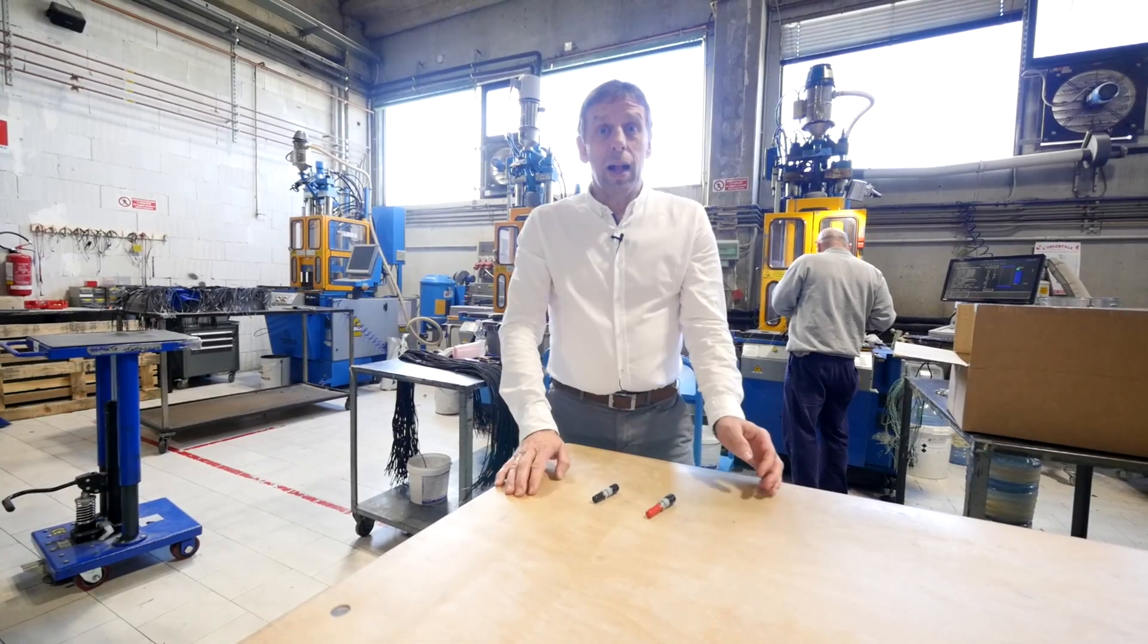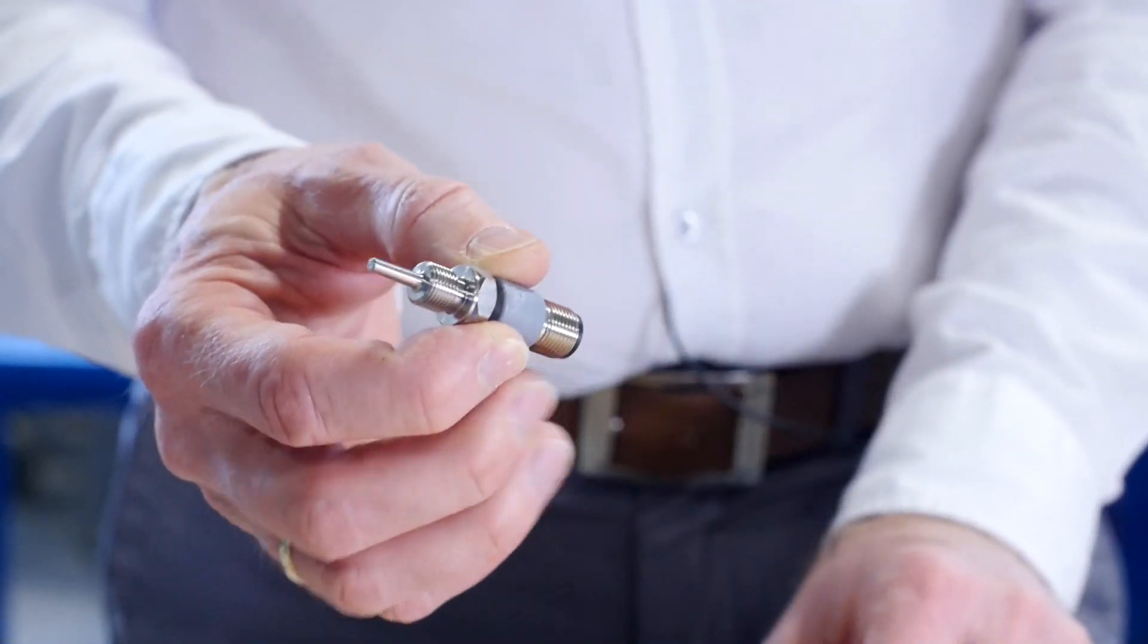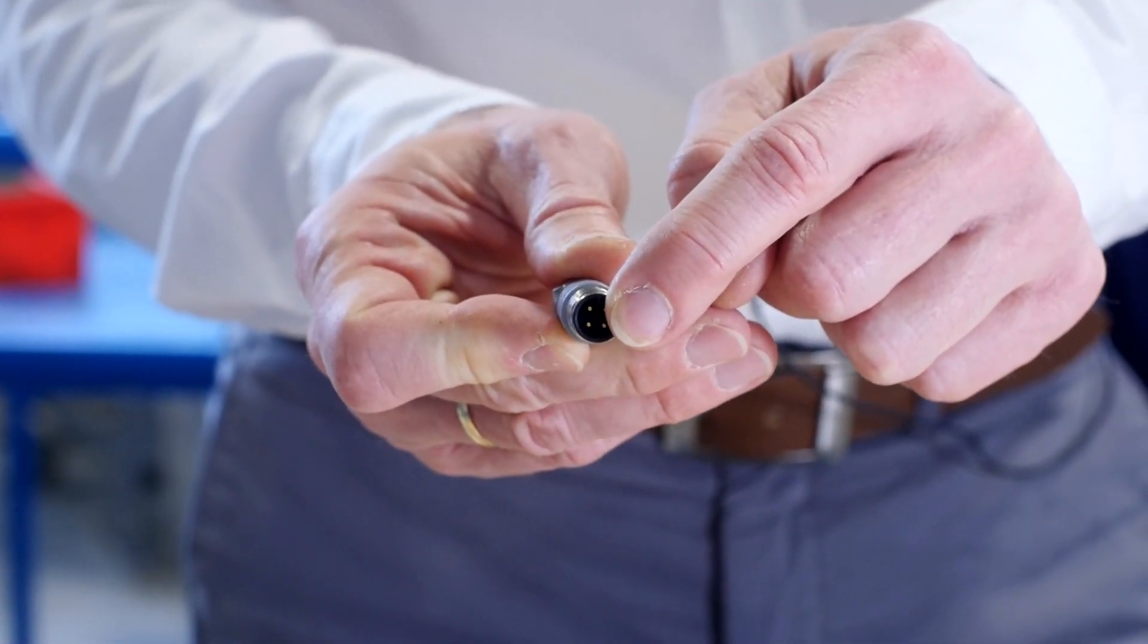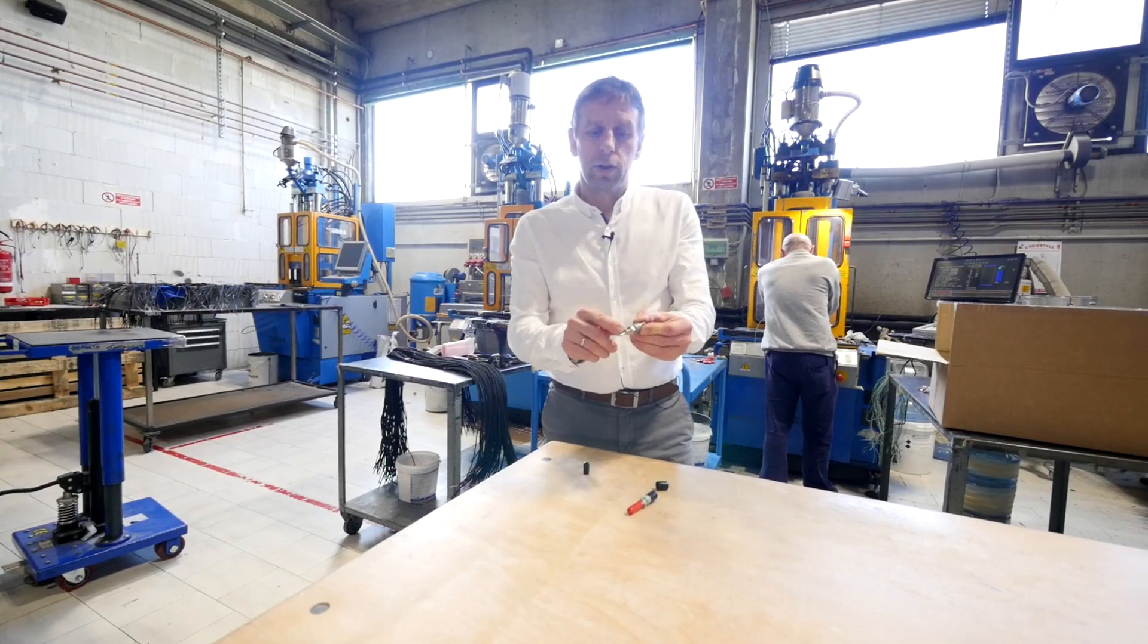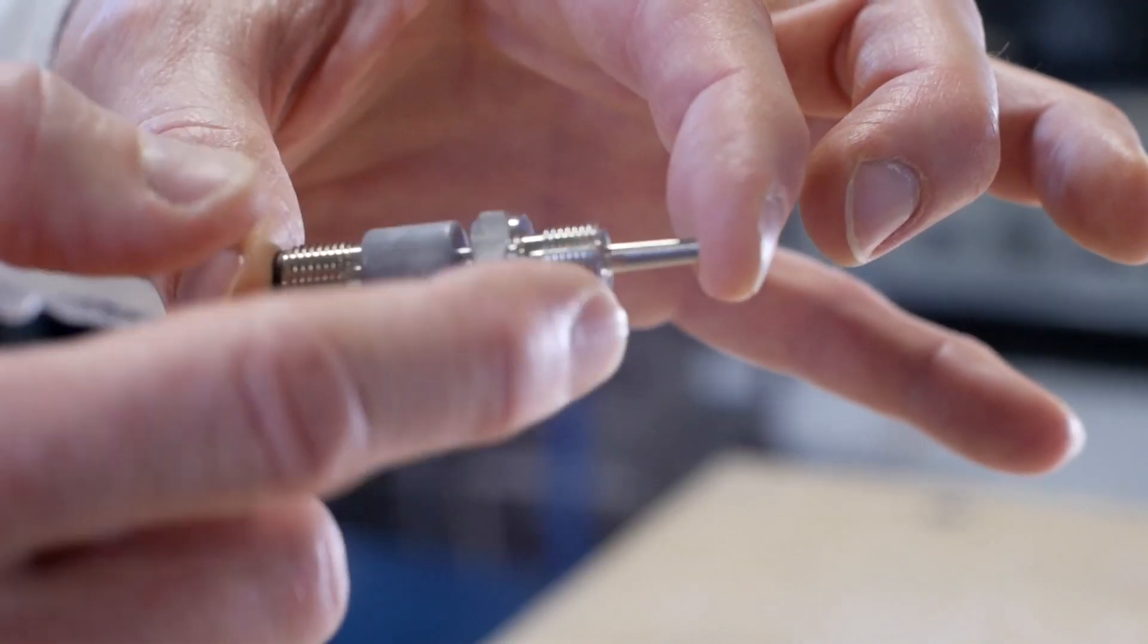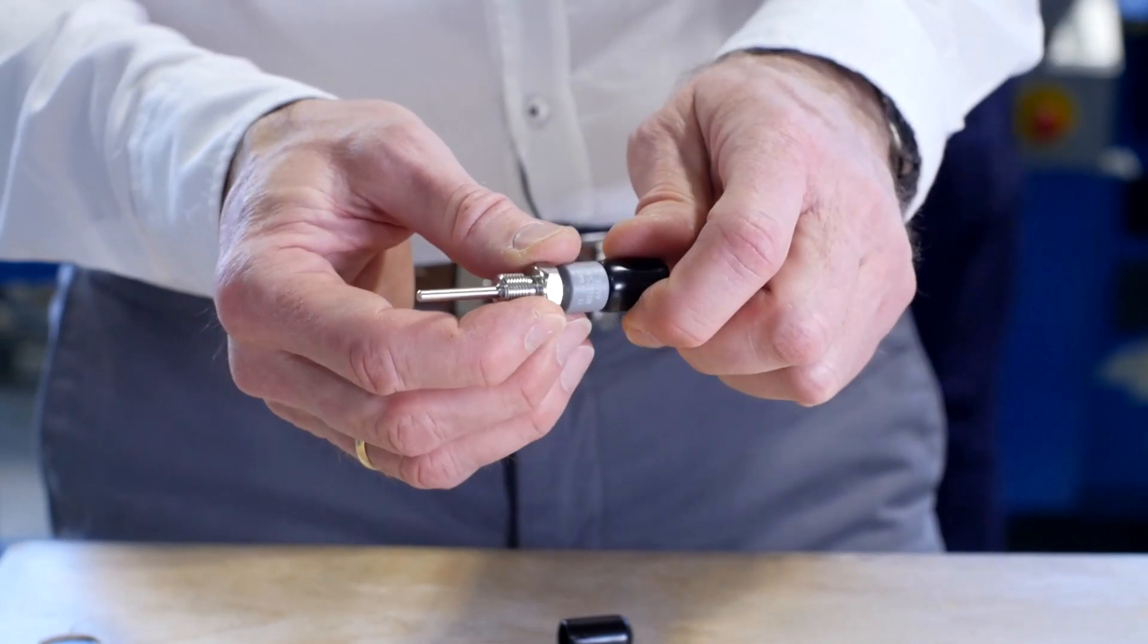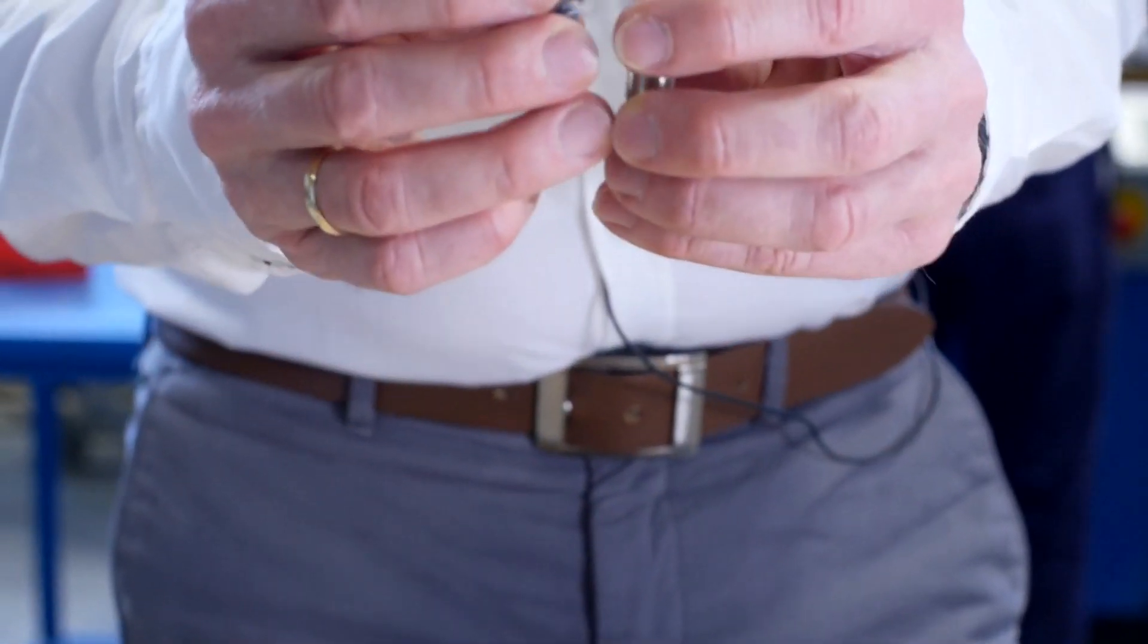The result is a robust and compact temperature probe, which is, due to the 4-wire connection, very accurate and easy to install due to the threaded connection. The design is optimized for quick response times and this kind of probe is available from stock in two lengths.